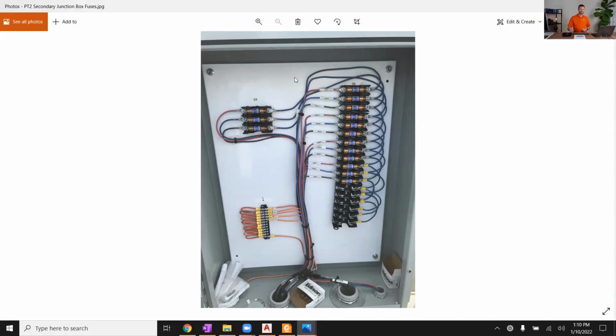Why do we use fuses in general, right? Not just on PT circuits. We're protecting against, well, yes, protection. What type of fault condition are we protecting against on our PT secondary circuits? Over voltages, good guess. It's actually more of the other side of things. It's more of the overcurrent situation. It's short circuits. There we go. That's what I'm looking for.